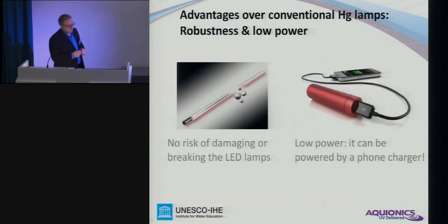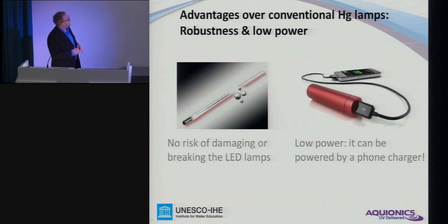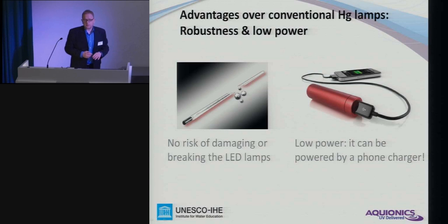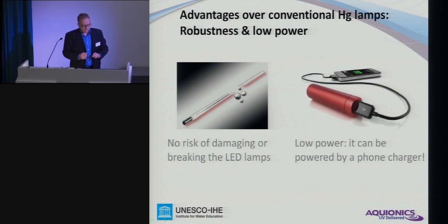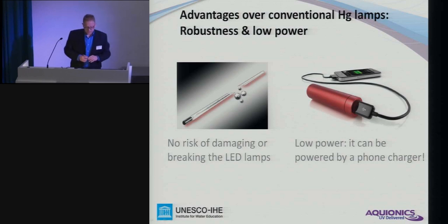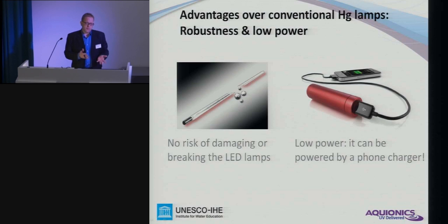With other advantages over mercury-based lamps, we have no risk of damaging or breaking the lamp. A mercury spill kit, as found today with every water treatment works, is not necessary anymore. The power consumption for individual LEDs is very low — you can charge them with your phone charger if you have the right connection. The lamps are operated on 6 to 30 volts DC, so operation with solar power or battery power is a realistic option with LEDs.